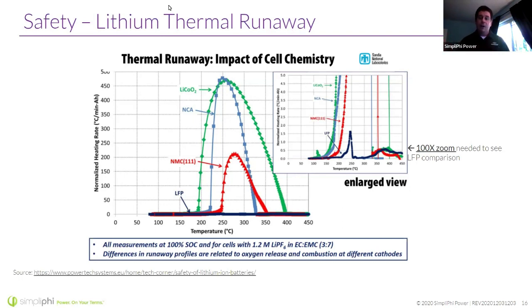So what this graph really demonstrates is that, under similar circumstances of high temperature—it could be a fire—the LFP chemistry is far safer. You're not going to have these high-energy events with these big curves, and in fact the energy curve you do get is rather small.